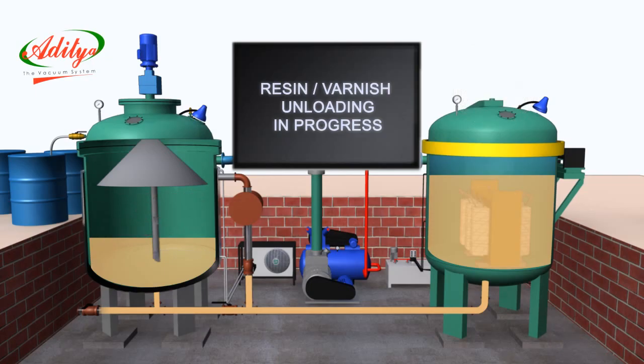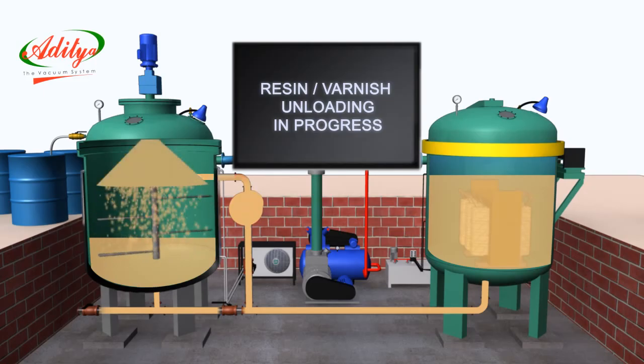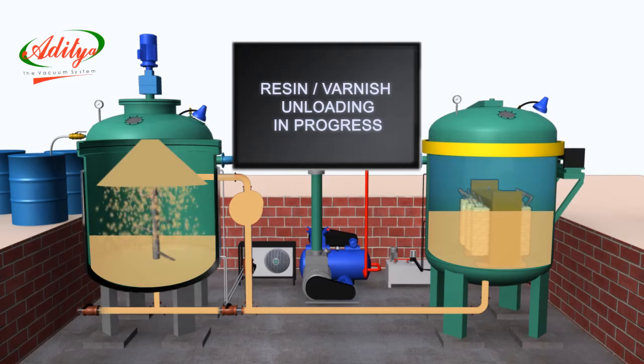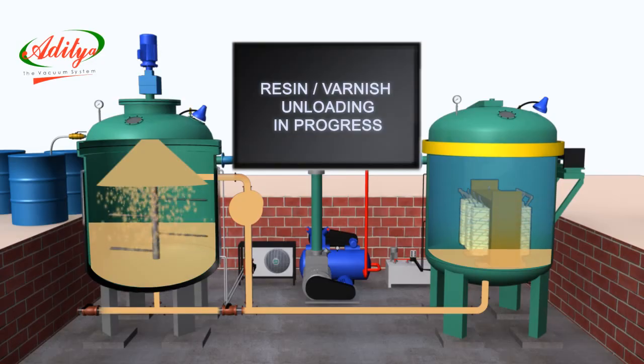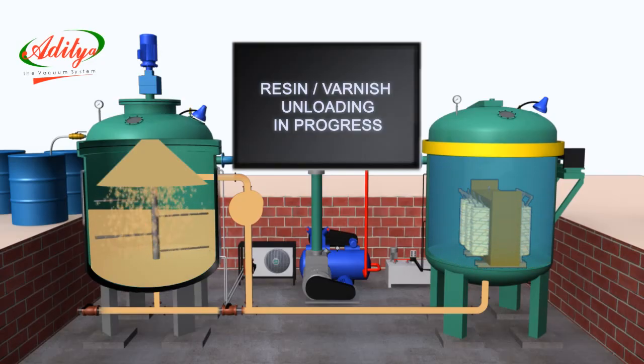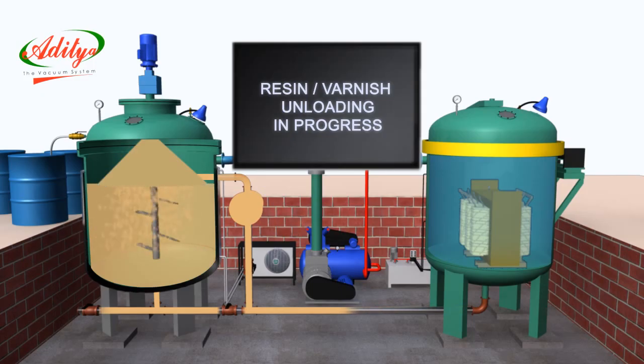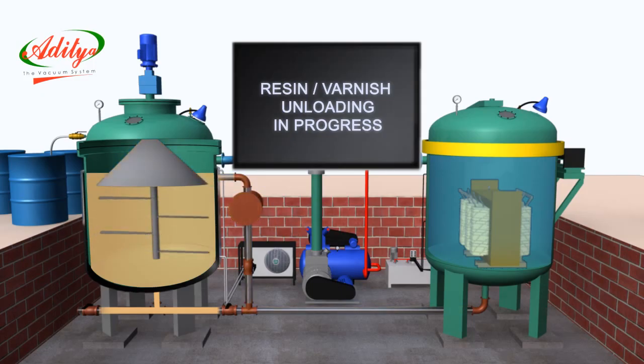Varnish unloading. After completion of pressure release, the next and final process is to unload varnish. The operator needs to turn the varnish load or unload switch towards unload position. During this process, the display screen shows Resin or varnish unloading in progress. After few minutes, the resin or varnish starts flowing from impregnation tank to storage tank. After completion of varnish unloading, operator needs to move varnish load or unload switch towards normal position. After completion of this process, the display will indicate the counting of cycles completed.